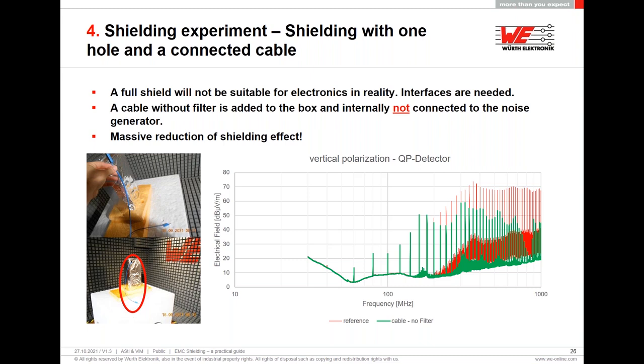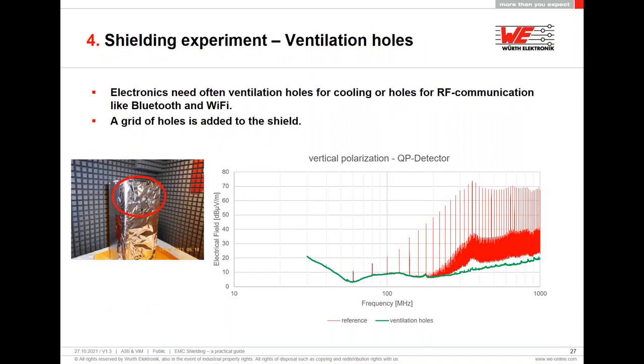The next point is heat. If you have a closed box without any ventilation, electronics heat up and we need ventilation holes. I added more holes with the cutter knife — a grid of small holes — and we can see that adding these small holes does not create problems in the emissions. This confirms what was mentioned in the basic theory part, and it works in reality.